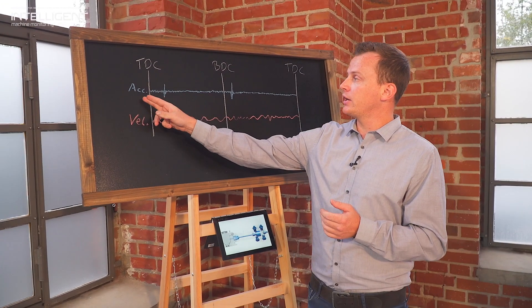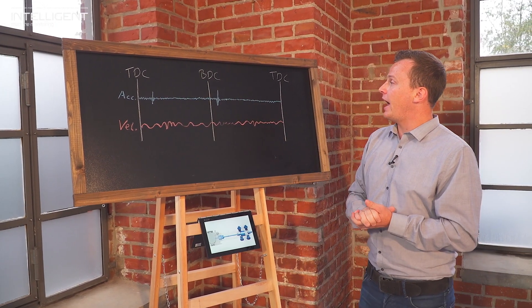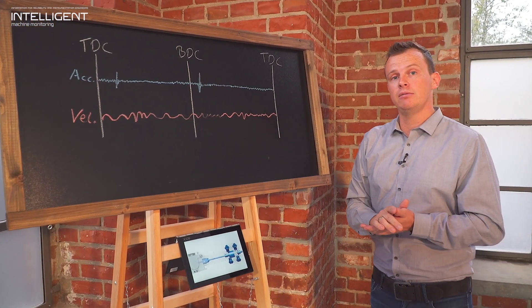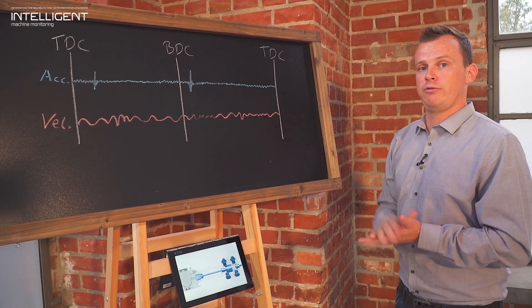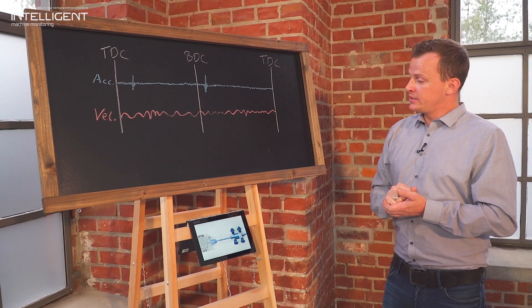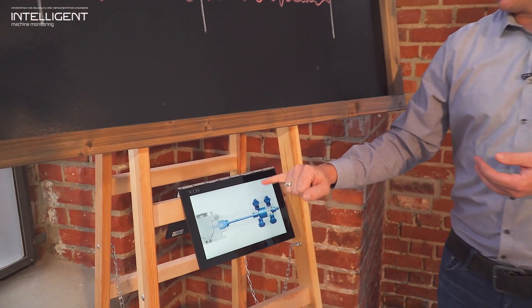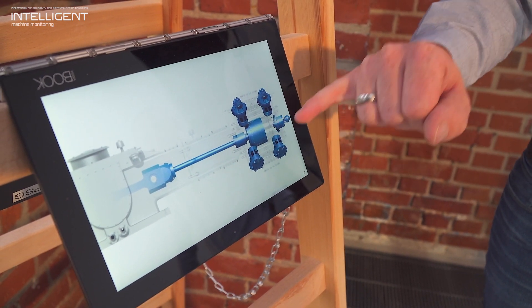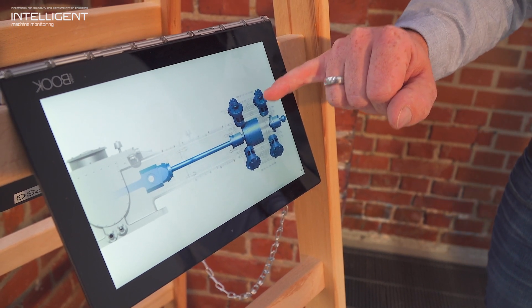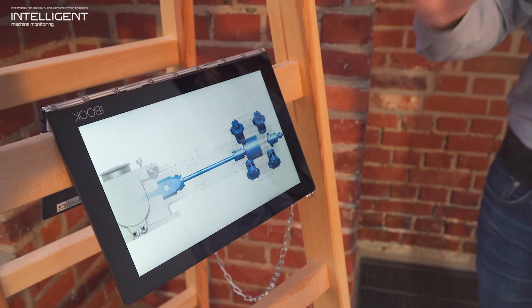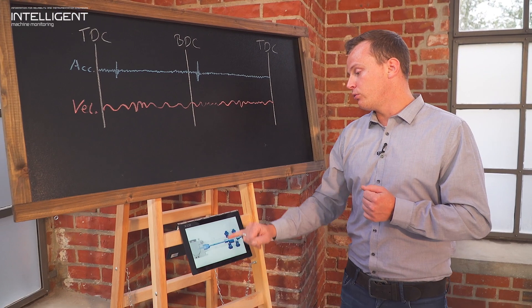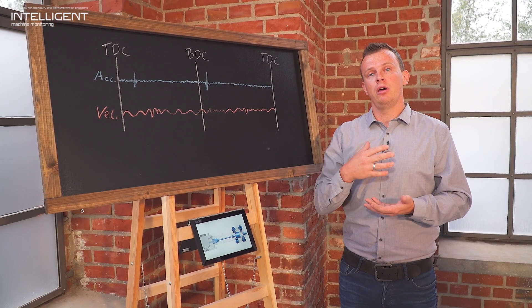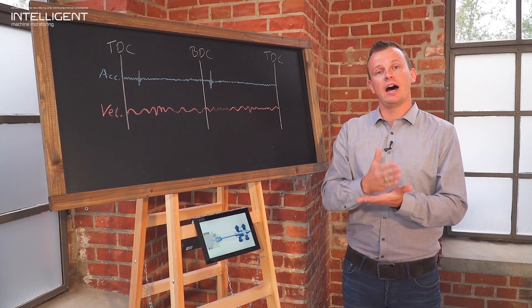On the other hand, we have the acceleration signal. As you can see, the frequency is much higher in the time signal over one revolution — from top dead center to bottom dead center and back — compared to the velocity signal, which is much lower in frequency. So where do we use these acceleration probes? These are mainly used on the cylinder head of the compressor, because we want to monitor the impacts from the different valves. These are high-frequency impacts, and each valve opening or closing will cause a vibration signal measured with the acceleration probe. Additionally, we use this probe on the crosshead area to monitor crosshead vibrations as well.